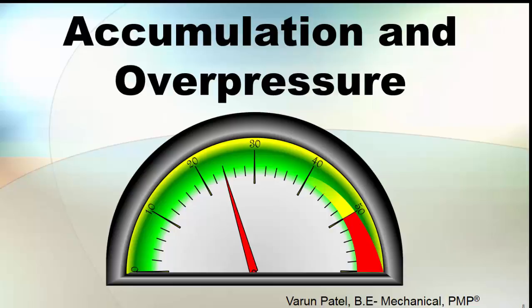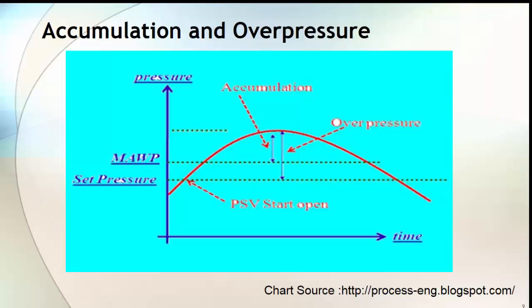Accumulation and Overpressure — these two terms are also related to Pressure Vessel and Pressure Safety Valve. Now check this Pressure vs Time graph for a Pressure Vessel fitted with a Pressure Safety Valve to protect the equipment from blast. The red curve line represents the pressure condition inside the equipment with respect to time. The lower dotted line represents PSV set pressure, which is a little more than operating pressure, and the upper dotted line represents Maximum Allowable Working Pressure.